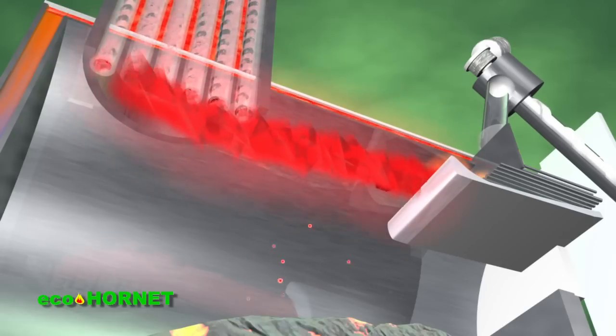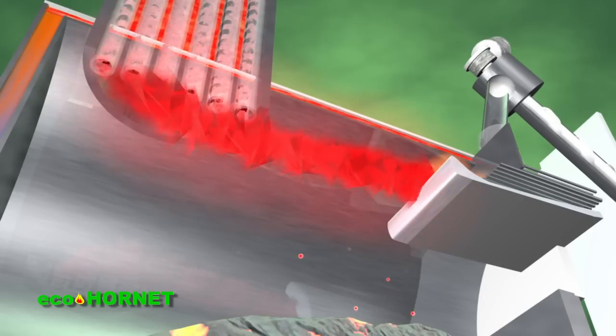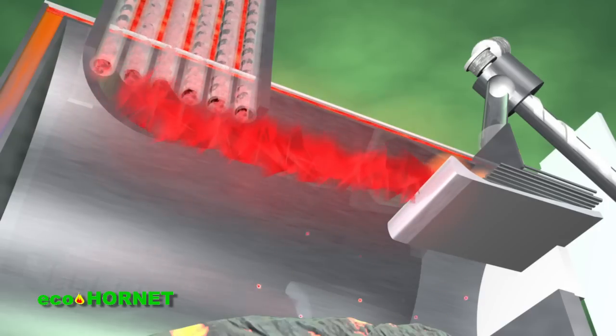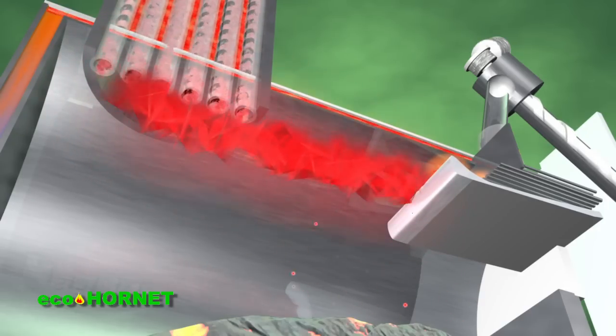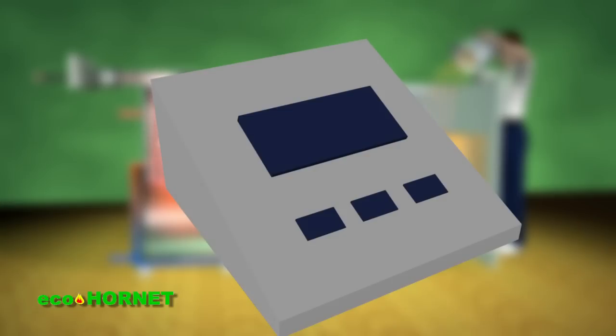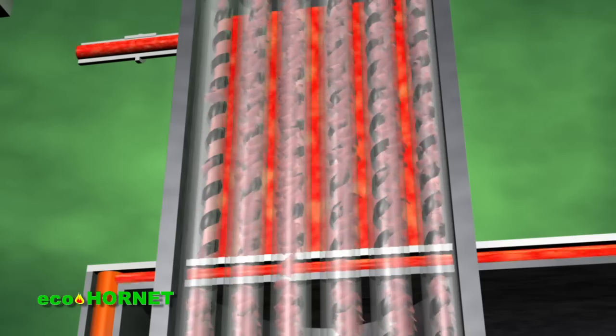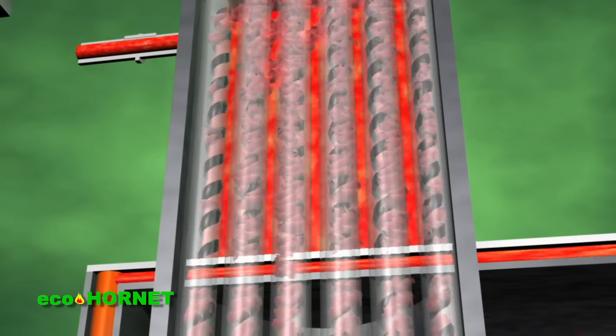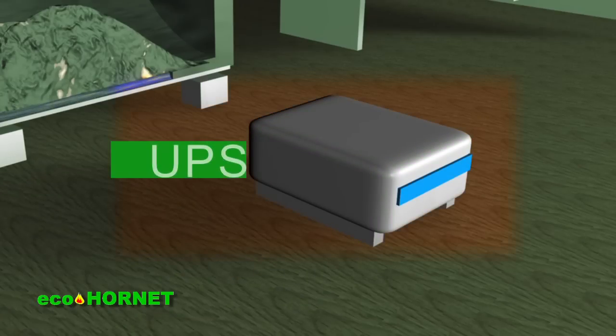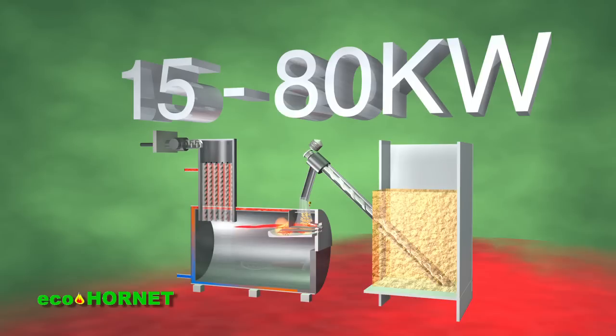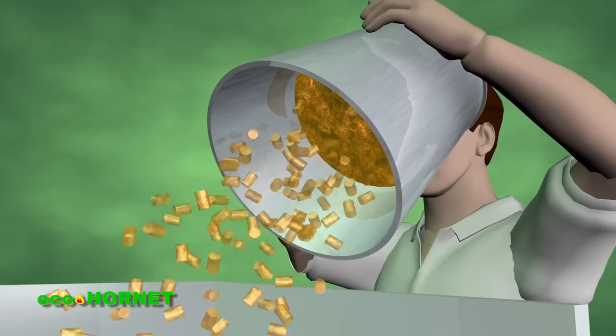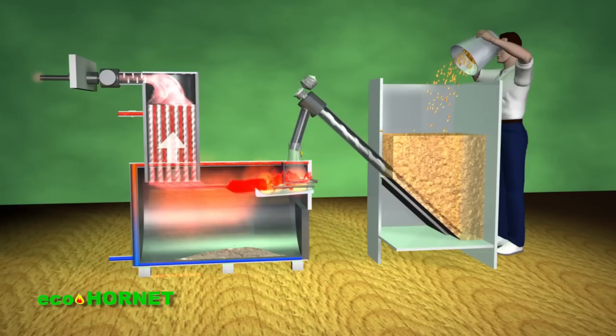Unlike other pellet-based heating systems on the market, EcoHornet heating systems do not require burner or nozzle cleaning devices in operations, since the burned gases do not contain any smoke. EcoHornet heating systems are extremely safe when in operation, the entire combustion and supply process being perfectly controlled and supervised by the automation system. In addition, to prevent overheating of the thermal agent, the automation system includes a UPS unit to keep the fan and the recirculation pump operational until full combustion of the fuel is achieved. The EcoHornet heating systems have powers ranging from 15 to 80 kilowatts, representing the latest technology for pellet-based heat generation, providing users with comfort and ease of use, constant high efficiency, lower fuel consumption, and maximum safety.